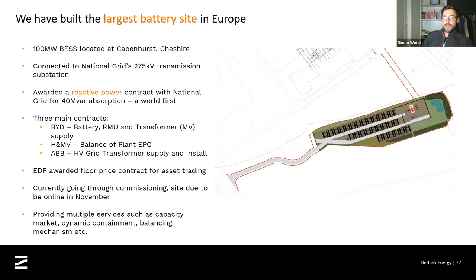It is connected directly onto the 275 kV transmission network. It is the only battery to have ever done that. Most batteries that have been delivered in the UK so far have been distribution connection, so they have been into 11 kV, 33 kV, or in some cases 132 kV. Never before has a battery connected directly onto the 275 kV network.